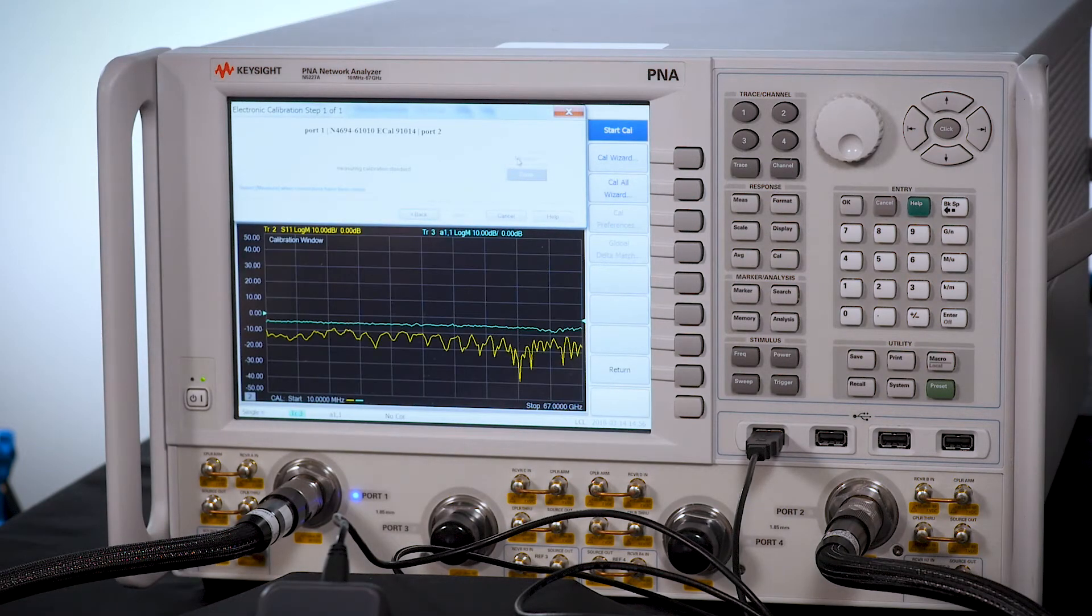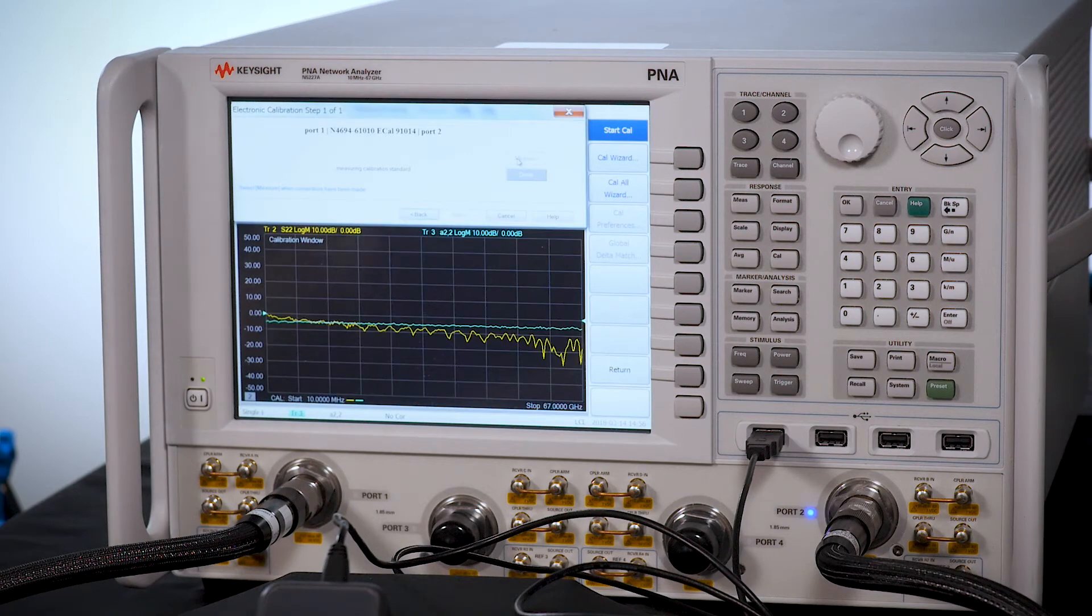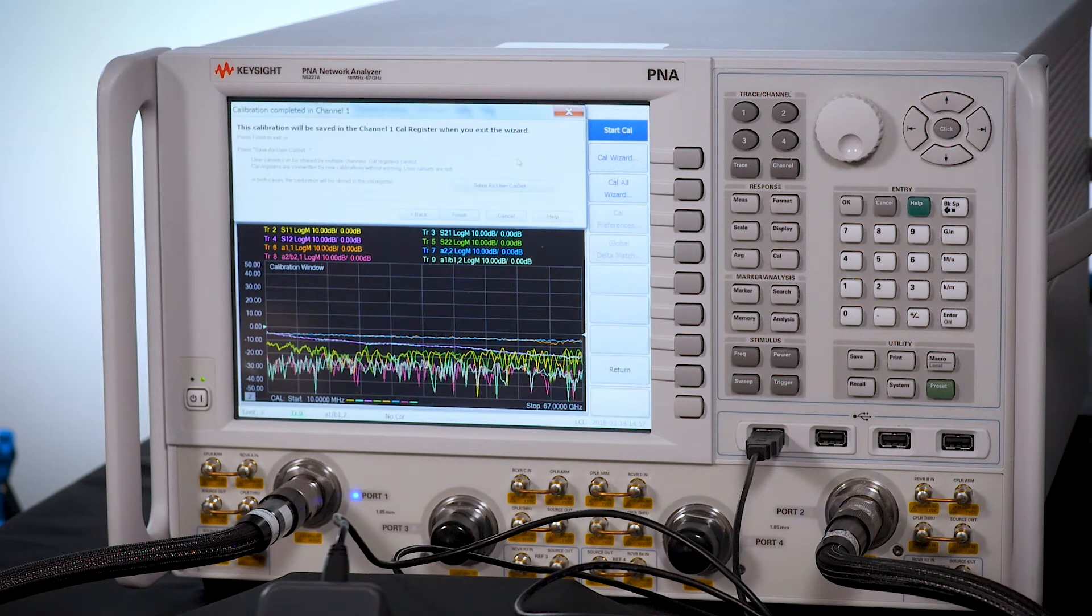Now the eCal is going to simulate short, open, load, and through connections just like it would with a mechanical cal, and it's done.